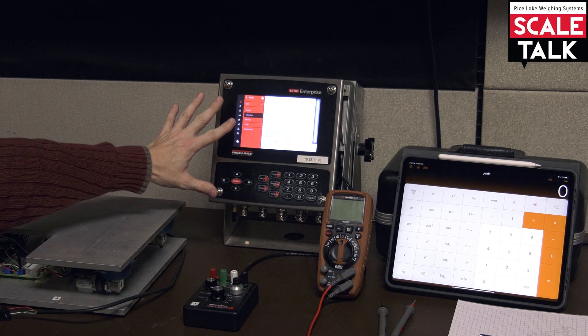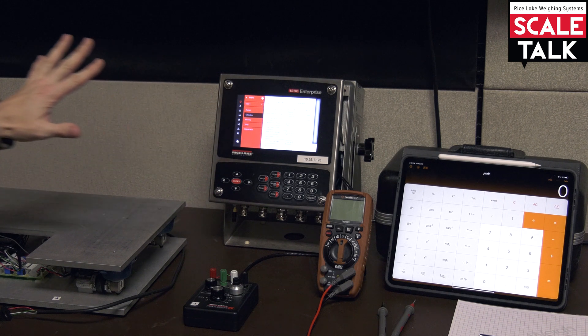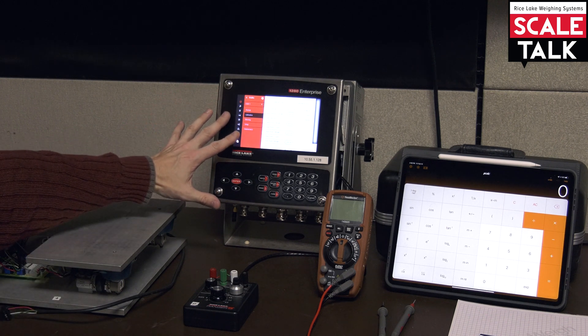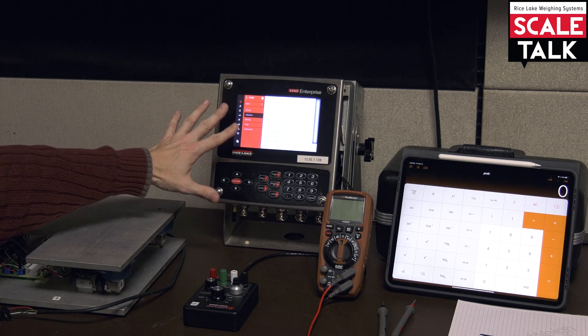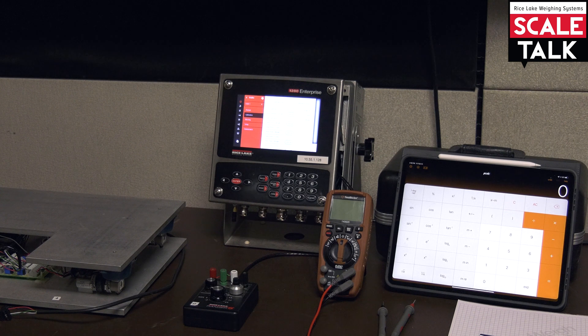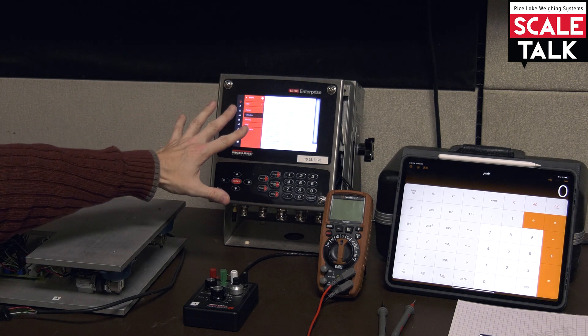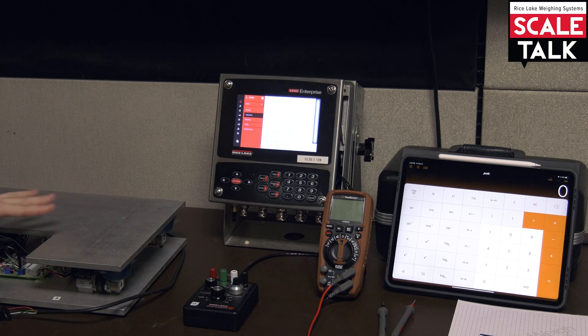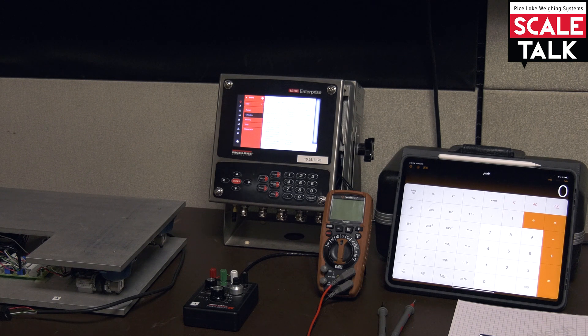So what we need to find out is what is the excitation voltage that's being provided by the indicator and we also need to know what the millivolt output is of the load cells in our system. You could use a nominal 10 volts for the 1280 and in this case I have a nominal 3 millivolt per volt system here. But if we want to try to make this at least a little bit more accurate, we can truly measure what's being output and we can take the average of all of the load cells in our system and use those values for our calculations.